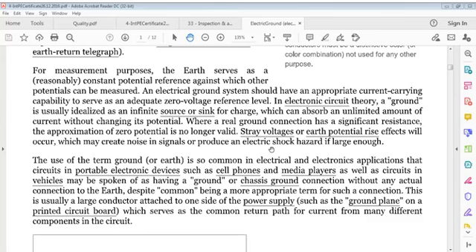For measurement purposes, earth serves as a reasonably constant potential reference against which other potentials can be measured. An electrical ground system should have an appropriate current carrying capability to serve as an adequate zero voltage reference level. In electronic circuit theory, a ground is usually idealized as an infinite source or sink for charge, which can absorb an unlimited amount of current without changing its potential. Where a real ground connection has a significant resistance, the approximation of zero potential is no longer valid. Stray voltages or earth potential rise effects shall occur, which may create noise in signals or produce an electric shock hazard if large enough.